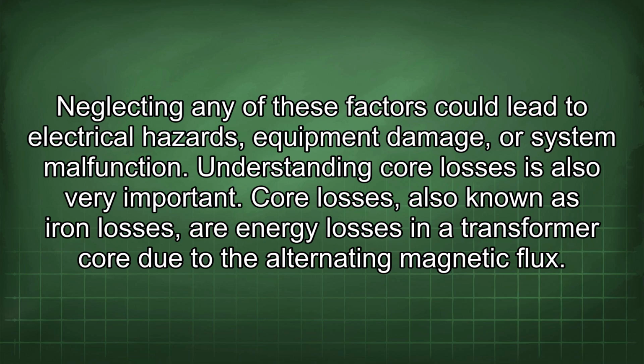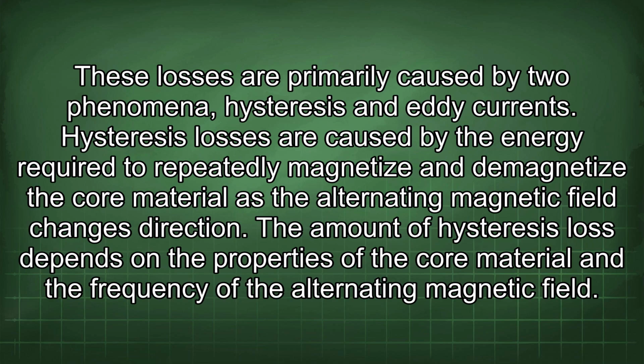Understanding core losses is also very important. Core losses, also known as iron losses, are energy losses in a transformer core due to the alternating magnetic flux. These losses are primarily caused by two phenomena, hysteresis and eddy currents. Hysteresis losses are caused by the energy required to repeatedly magnetize and demagnetize the core material as the alternating magnetic field changes direction. The amount of hysteresis loss depends on the properties of the core material and the frequency of the alternating magnetic field.